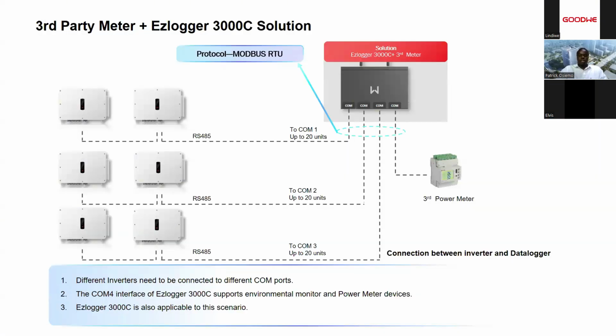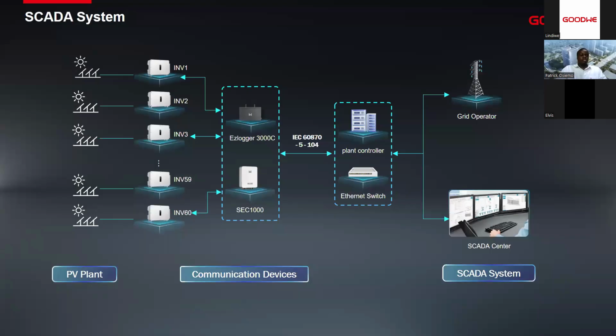Now, in case there are plans that you would like to use third-party, let me say, smart meters, the Ezlogger 3000C can be integrated with such kind of system. Now, in cooperation with the GT series, with the various ports, you can do a maximum of 20 GT series inputs on each COM port of the Ezlogger 3000C. And on the COM port, you can connect the third-party smart meter. We do have a compatibility list which you can unveil on demand. And yes, through this, you can achieve the various functions, for example, the export limit, the load monitoring and such of your PV system. So not only the GM330 and the GM1000C are compatible in these PV solutions, but yes, we do have a list of third-party smart meters that are compatible with the Ezlogger 3000C.